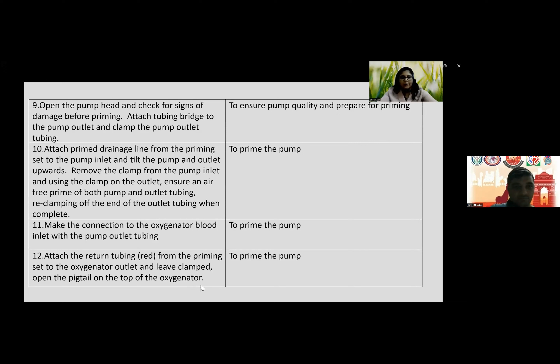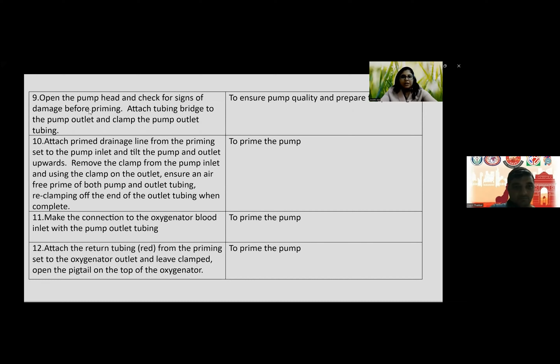Then you make the connections to the oxygenator blood inlet with the pump outlet tubing and you attach the return tubing, red, from the priming set to the oxygenator outlet and leave it clamped. Open the pigtail onto the top of the oxygenator. You then gently release the clamp on the pump outlet and slowly prime the heat exchanger up to the pigtail at the top of the oxygenator. You close off the pigtail when fluid is detected and use the P1 pigtail to remove any air present within the heat exchanger. So the P1 pigtail is the one which is pre-pump and that is used to measure the pressures.